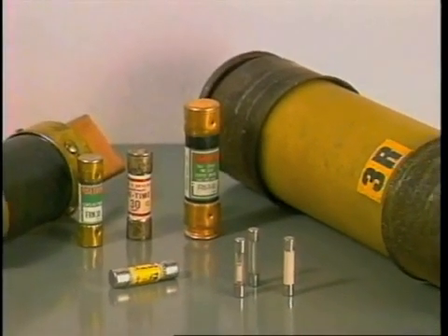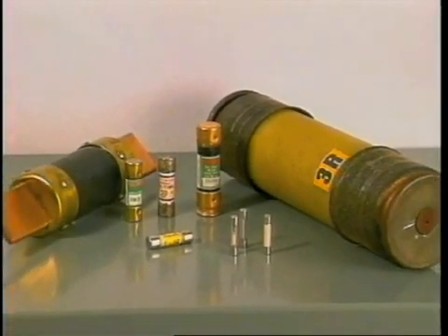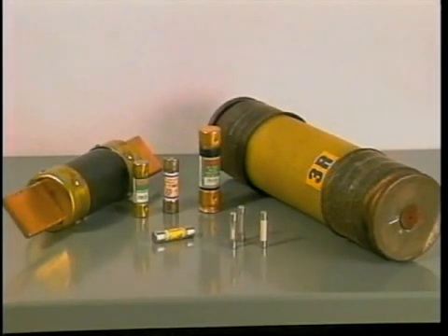One of the more reliable types of overcurrent protective devices is the fuse. The fundamental element of a fuse consists of a fusible link or links enclosed in a tube and connected to contact terminals. The electrical resistance of the link is very low, and it acts as a conductor. When current in the circuit exceeds the fuse size, the link melts and opens the circuit to protect the conductors, other circuit components, and equipment.